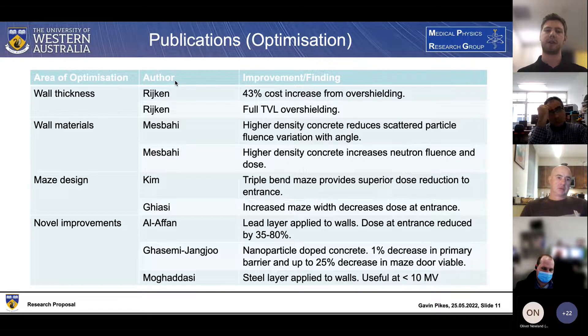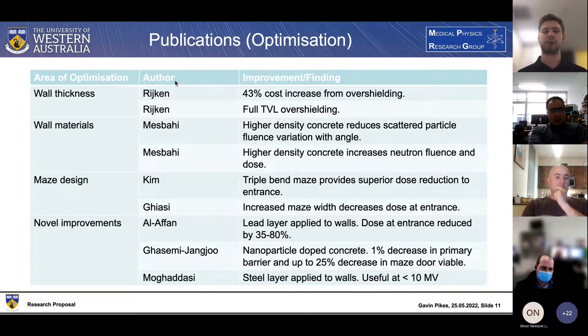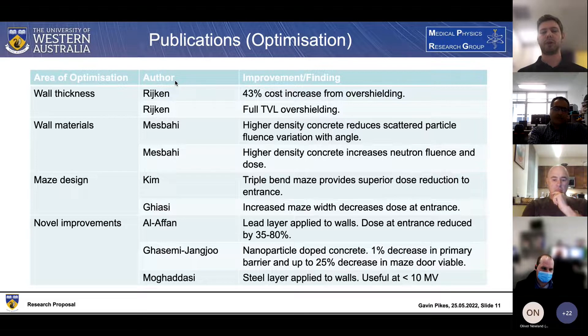He also found that a lot of these equations have resulted in a full tenth value layer of over-shielding at the primary barrier, which can quite easily be reduced while still maintaining adequate radiation shielding capability. In terms of wall materials, a lot of different materials have been tested, but there's been a big focus on high density concretes recently.